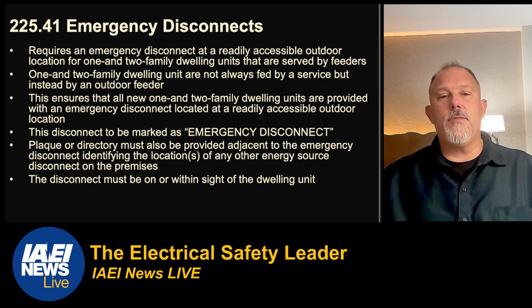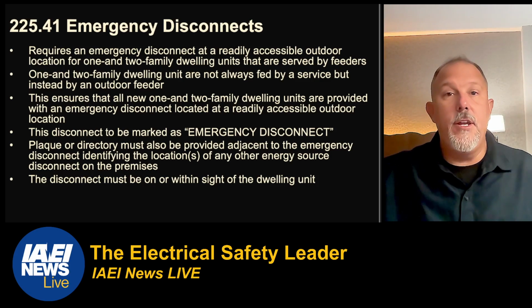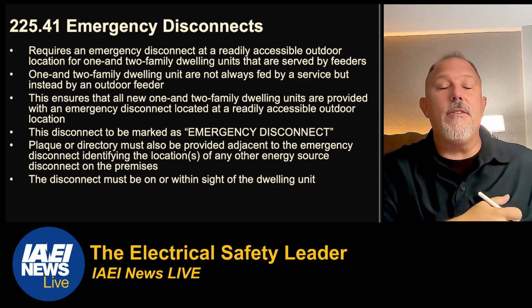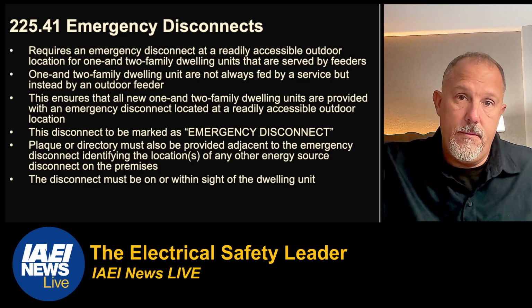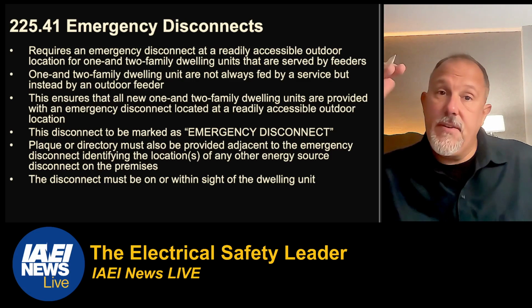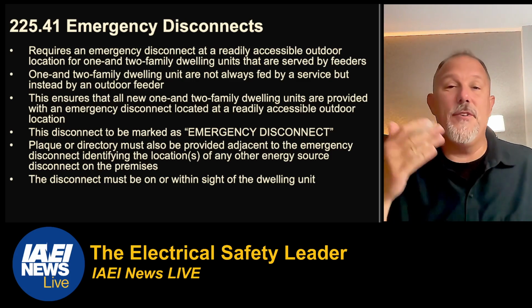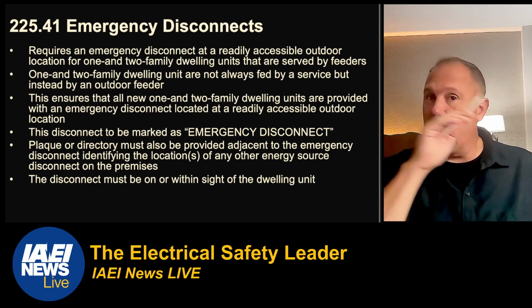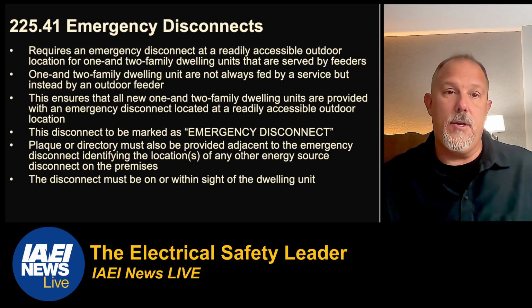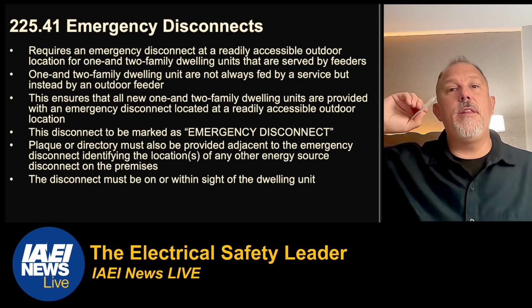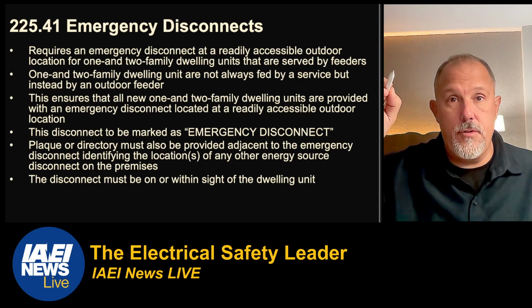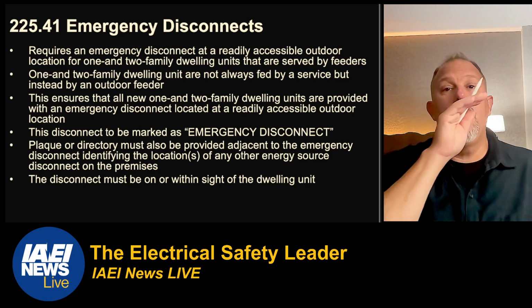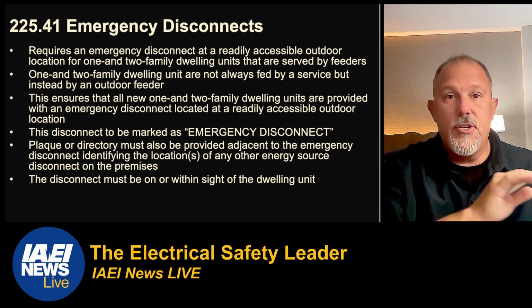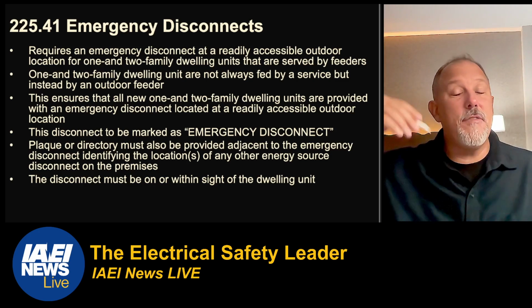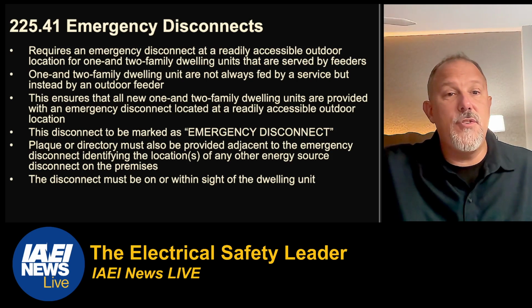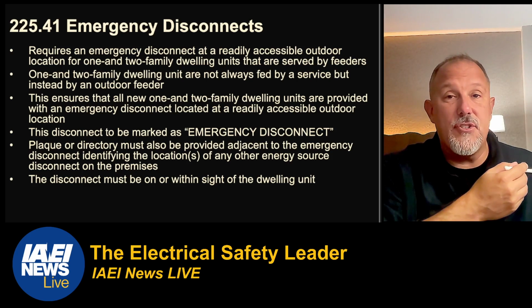So here's what you had. Here was the example that we were given. The service is, say, out at the road, and maybe even down the road, and you may not even know which service is for which home on that road. What they wanted to do, instead of putting the emergency disconnect out there on the road, was put it near the house. So you're going to have an outside feeder. If your service is out there at the road, then you're going to have an Article 225 feeder that has to feed the structure.